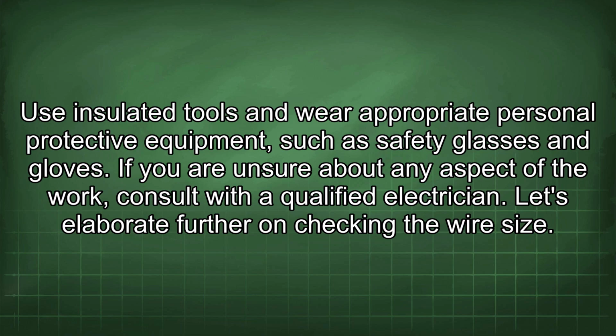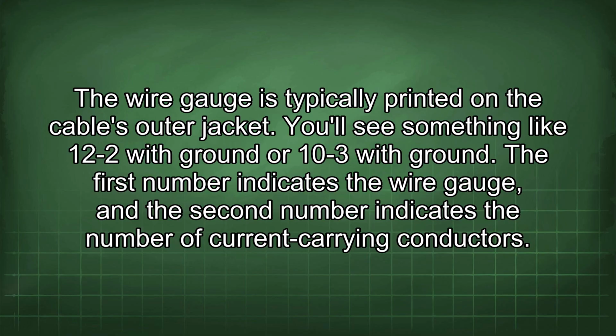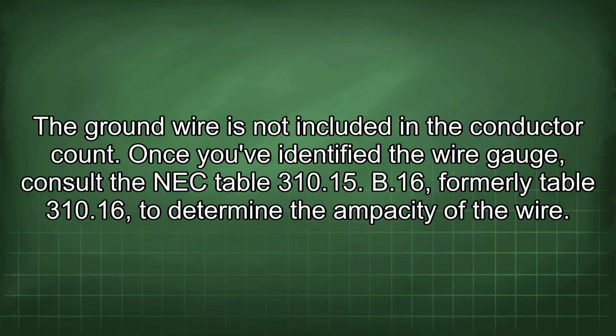Let's elaborate further on checking the wire size. The wire gauge is typically printed on the cable's outer jacket. You'll see something like 12-2 with ground or 10-3 with ground. The first number indicates the wire gauge, and the second number indicates the number of current carrying conductors. The ground wire is not included in the conductor count.